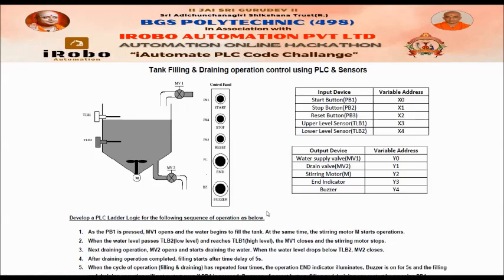Now I will explain the sequence of operation. As PB1 (start button) is pressed, MV1 opens, meaning filling starts, and water begins to fill the tank. The low level sensor TLB2 will turn on first as the water rises, and then the high level sensor TLB1 will turn on. At the same time as PB1 is pressed, the stirring motor M also starts operation.